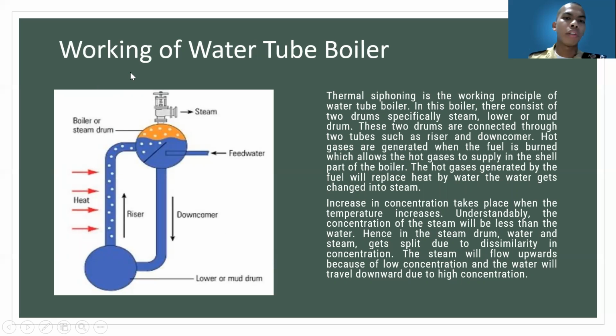So this is the working of the water tube boilers. Thermal siphoning is the working principle of the water tube boilers. This boiler consists of two drums, specifically the steam drum and the lower or mud drum. These two drums are connected through two kinds of tubes, such as risers and downcomers.